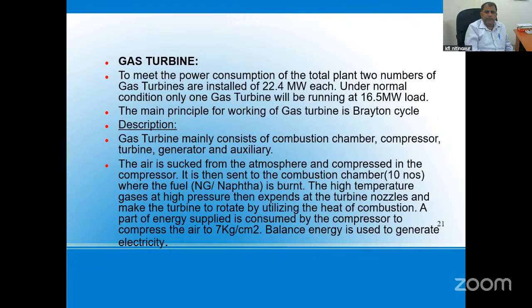Fuel may be natural gas, diesel, naphtha, as per the designer. Actually, our gas turbine, when initially commissioned, was running on naphtha, but due to unavailability and its low calorific value, we replaced naphtha with natural gas.